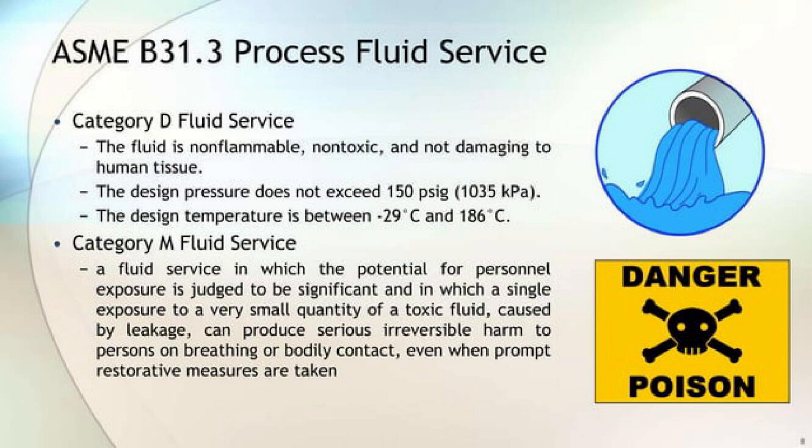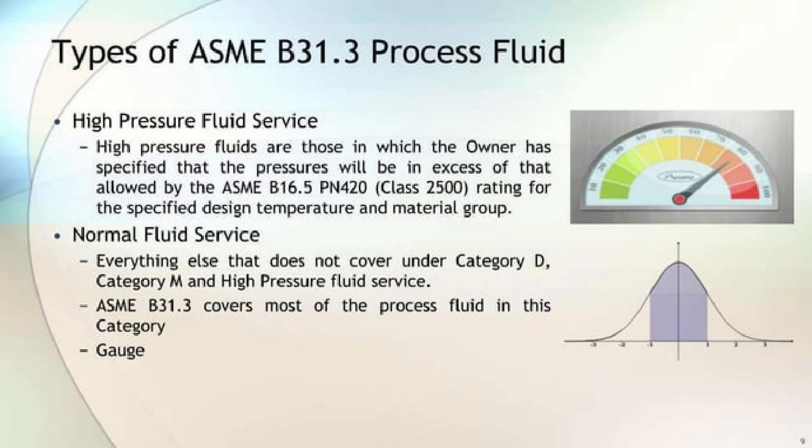Category M Fluid Service: a fluid service in which the potential for personal exposure is judged to be significant, and in which a single exposure to a very small quantity of toxic fluid caused by leakage can produce serious irreversible harm to persons on breathing or bodily contact, even when prompt restorative measures are taken. Type 1 — High Pressure Fluid Service: high pressure fluids are those in which the owner has specified that the pressures will be in excess of that allowed by the ASME B16.5 PN420, Class 2500 rating for the specified design temperature and material group.